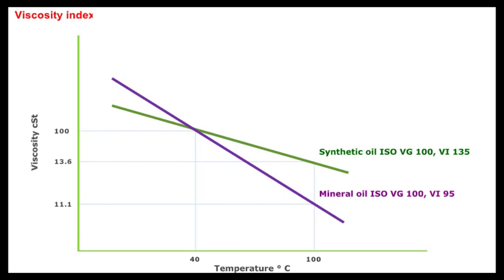In the example shown here, two ISO VG100 oils with different viscosity index are compared. Although at 40 degrees Celsius the viscosity is the same, at 100 degrees Celsius the oil with a viscosity index of 135 reports a higher value compared with the oil having a viscosity index of 95.